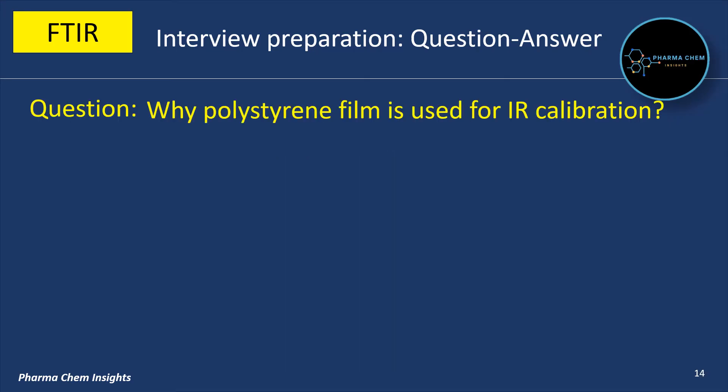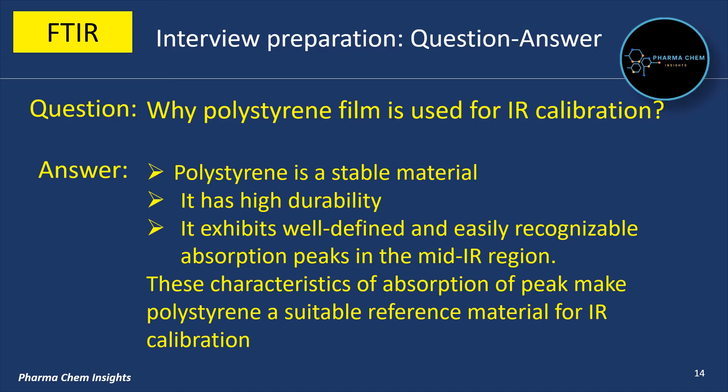Why is polystyrene film used for IR calibration? It is a stable material with high durability. It exhibits well-defined and easily recognizable absorption peaks in the mid-IR region. These characteristics make polystyrene a suitable reference material for IR calibration.